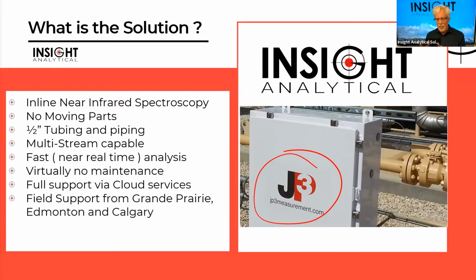Multi-stream capable, can handle more than one measurement point. Fast, near real-time analysis, often under 15 seconds. Future software upgrades are coming out. It's going to get that even faster. There are virtually no maintenance devices. There's very few user serviceable parts in it. The one thing that does require any possible maintenance is cleaning the cell windows, which is about a 1/2 hour task. So it can be maintained very easily.